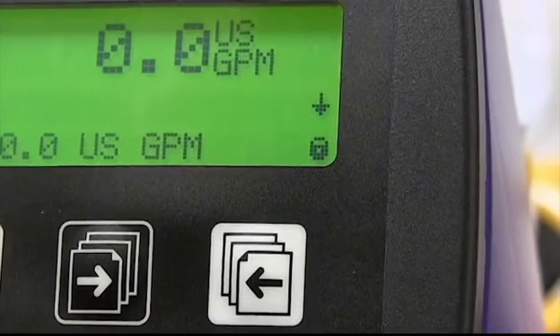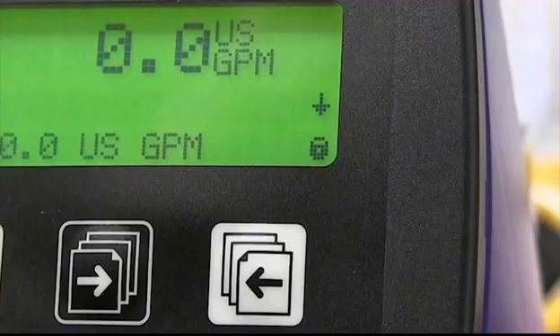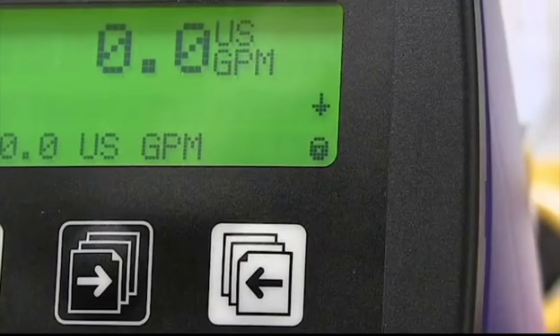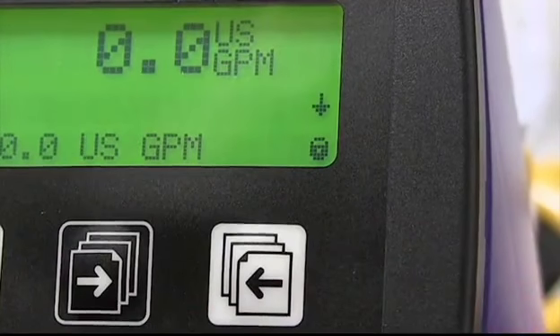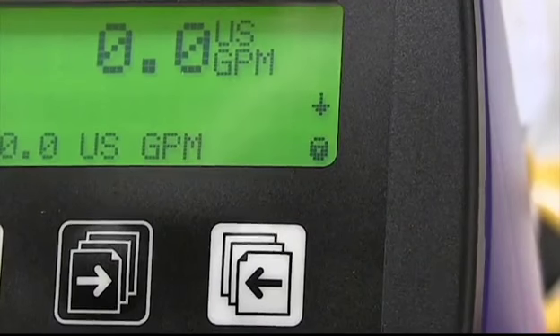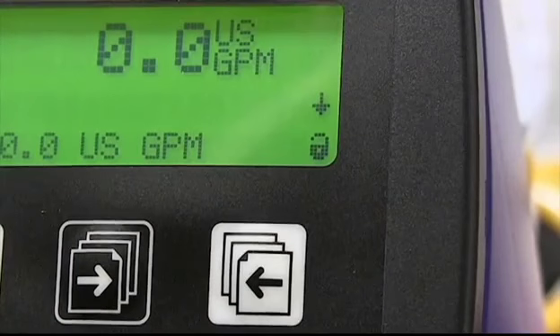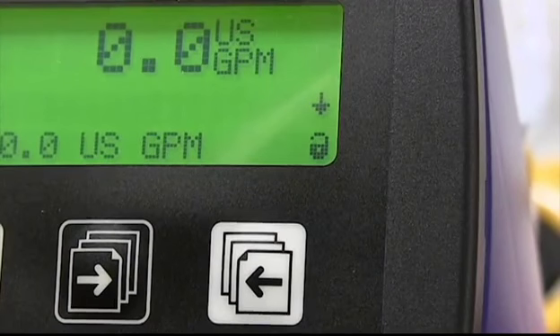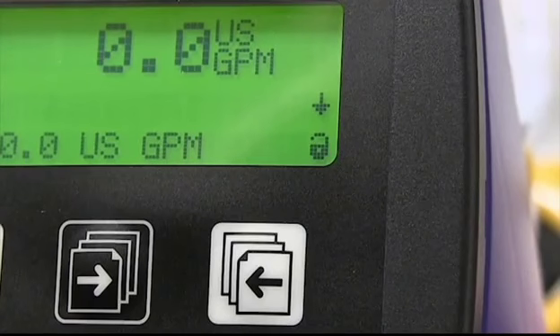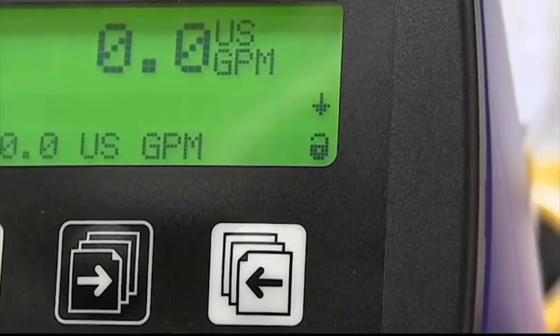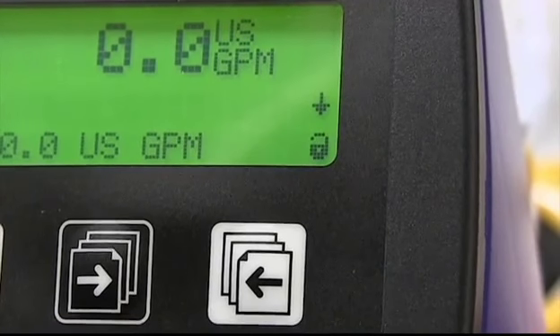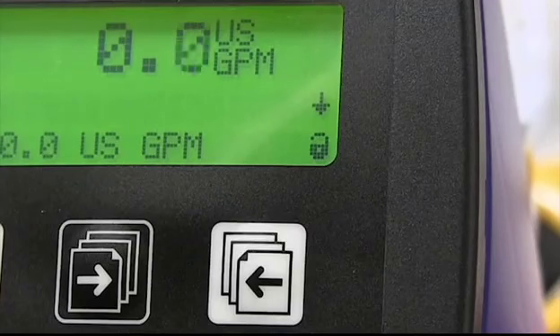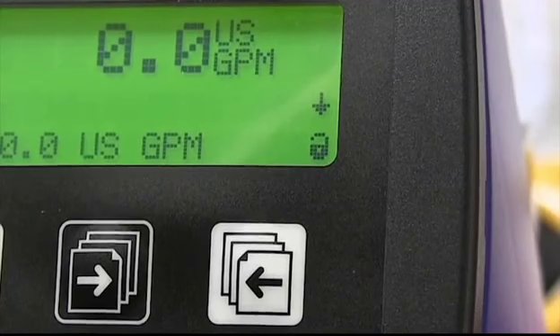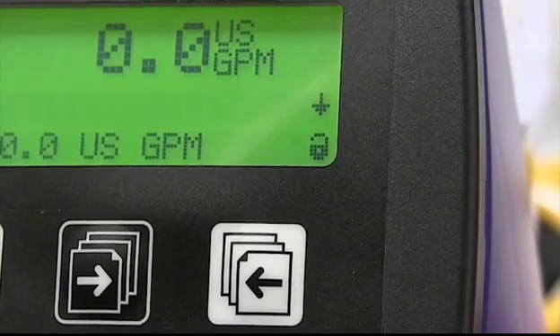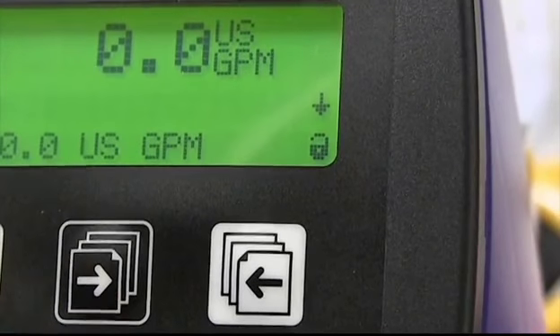Say for instance you have a receiving device, a PLC or whatever, that needs to be ranged to, I don't know, 30 gallons per minute as opposed to 40. So simply press the lock unlock once, and the cursor appears underneath the 0 on the left hand side. Simply press the button in the middle at the bottom until you get to the 4. Let's see here, this would be this button here. Keep on going till you get to the 3. Okay, 30 gallons per minute.